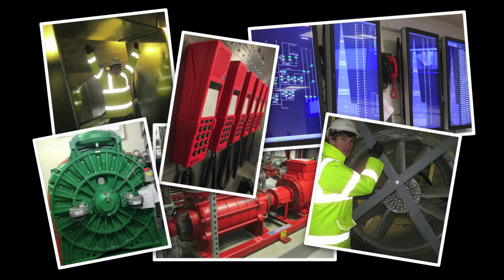And then there's the challenge of pumping large volumes of water from the bottom of the building to the top for the sprinklers and wet risers that the fire brigade will plug their hoses into. All of these systems must have a high level of resilience, so duty standby arrangements are used for the chillers, pumps, fans and other equipment, which have generator-backed power supplies so that they can be called upon at all times. These systems also need to know what to do depending on what happens in the building and where.